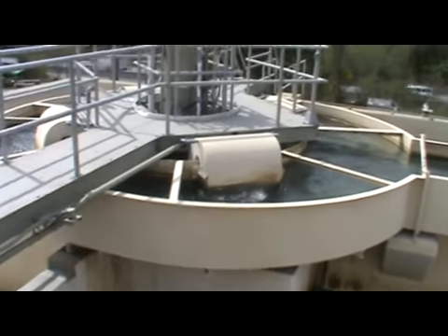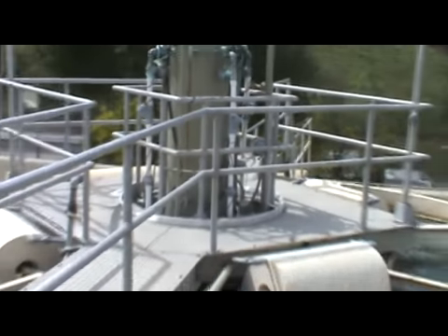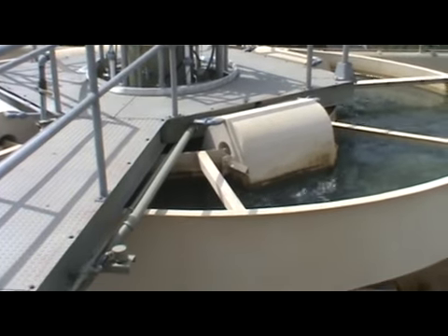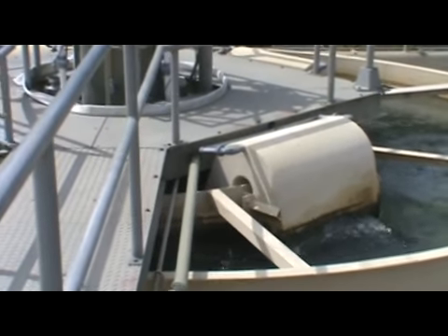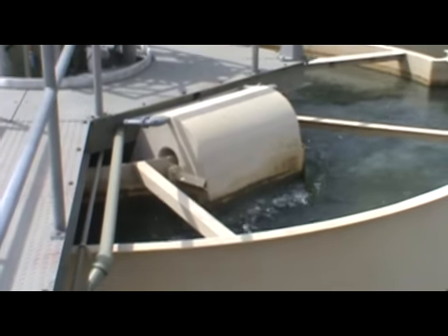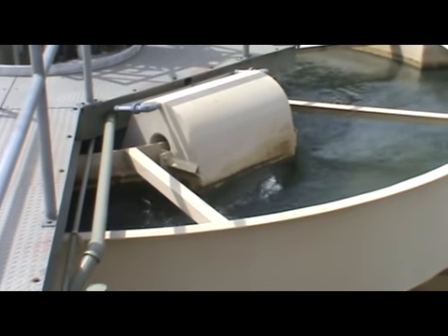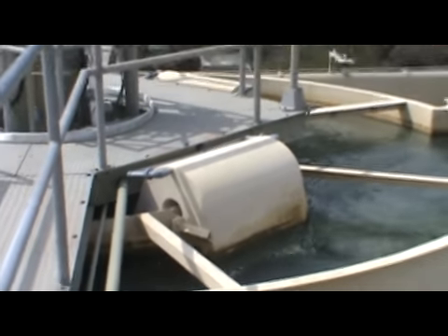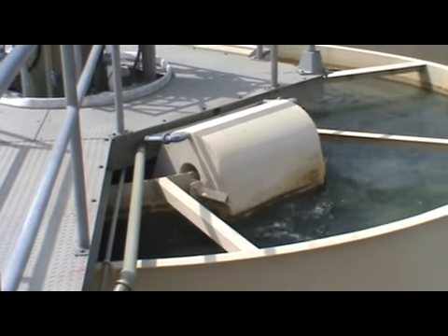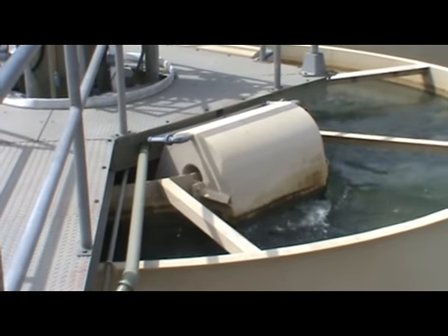If you see this structure right here, this vacuum tank creates a suction, and as that vacuum creates a suction, it sucks the water over the trough and down into the other side, which then feeds into the individual filter cells. That is how we bring a cell online: we create that suction and the water pulls into those filter cells. When you want to take a filter offline, they break that suction and the air gap between them is gone. Let's take a look at one of our individual filter cells and see how it works.